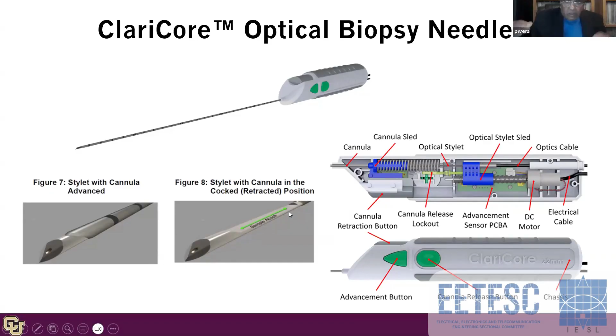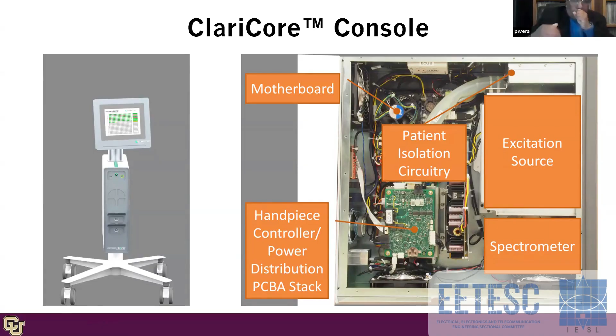This is the ClariCore console. Fairly straightforward. There's a motherboard, and there's patient isolation circuitry because you don't want to electrocute the patient. And then the handpiece and the power distribution board, which controls the biopsy needle. Then the excitation source, which are the light sources that you send to the fiber, and then the spectrometer is the one that reads the signal back.